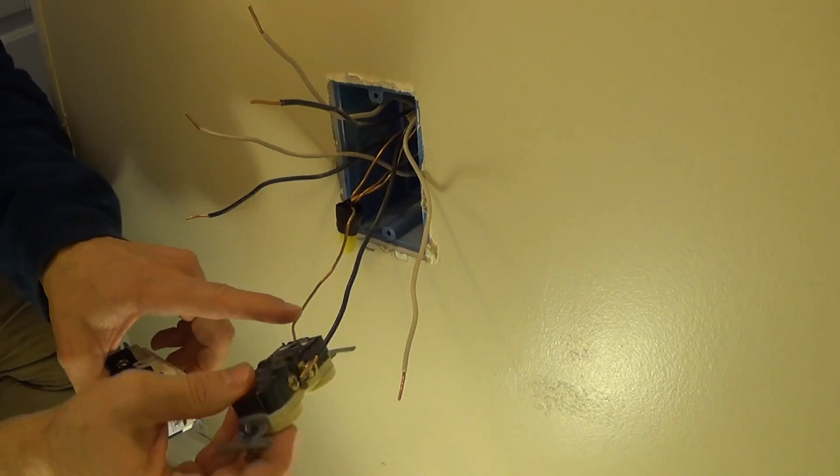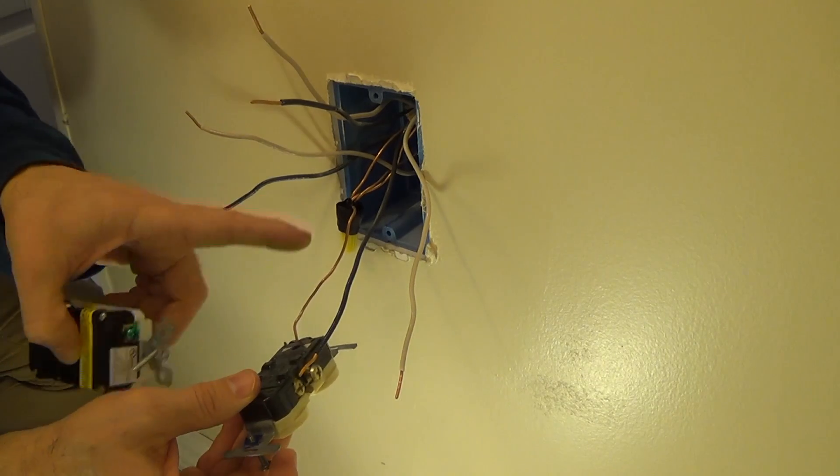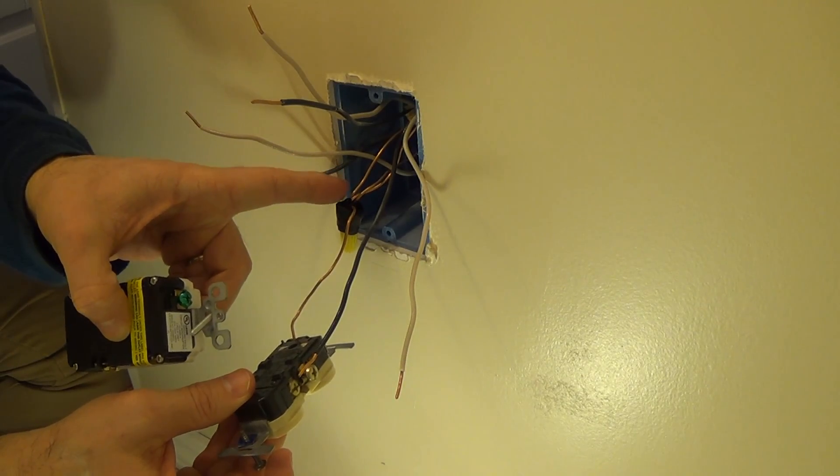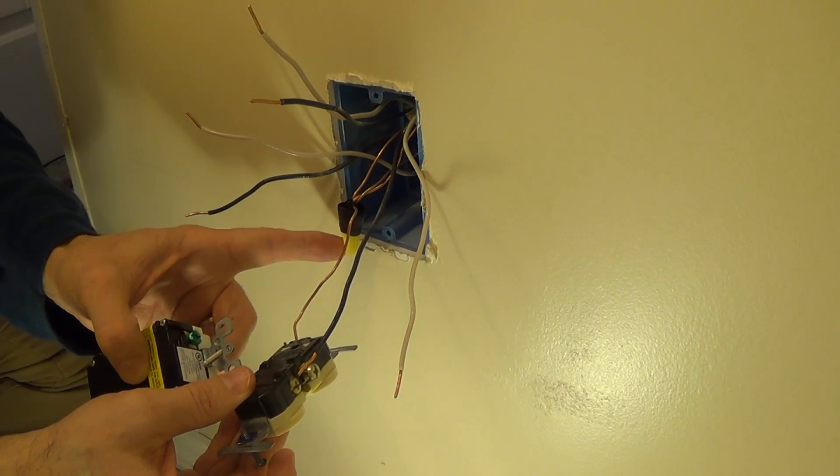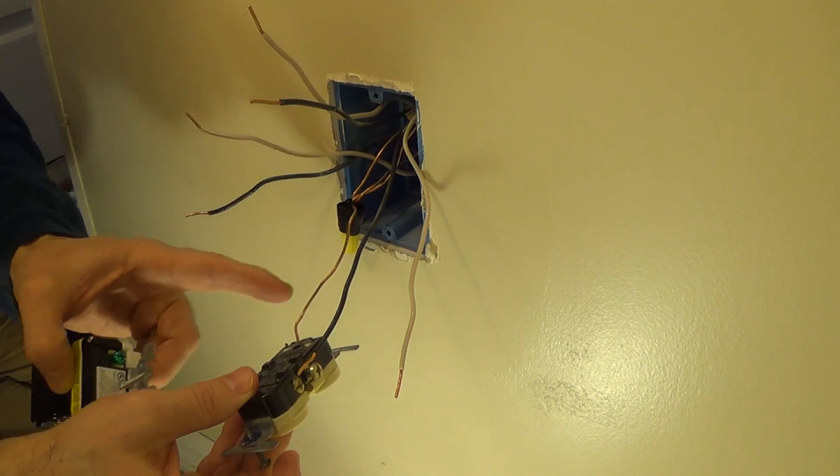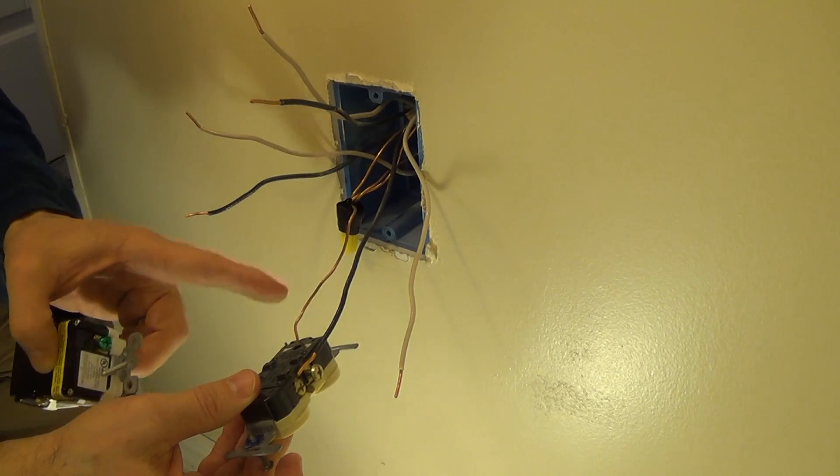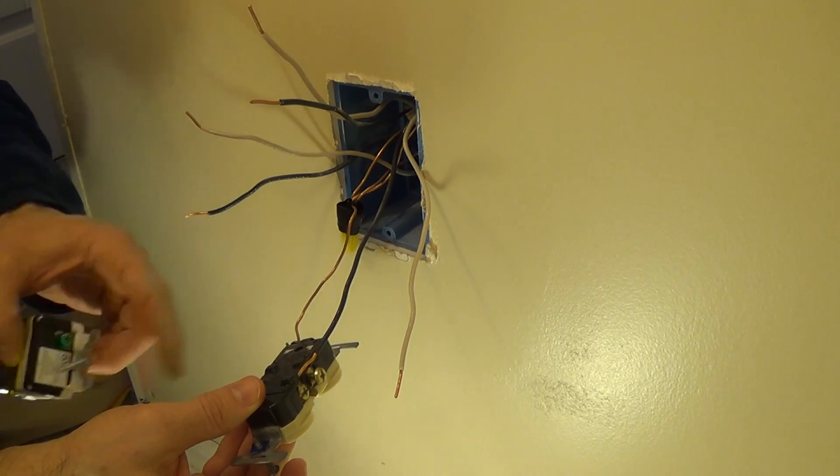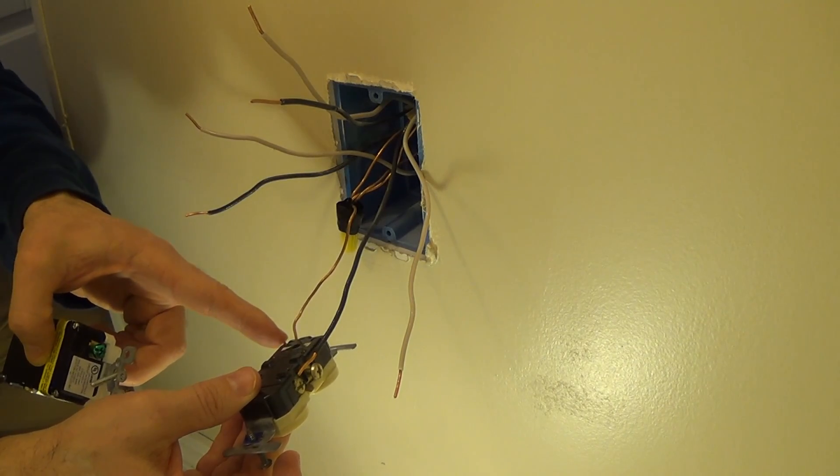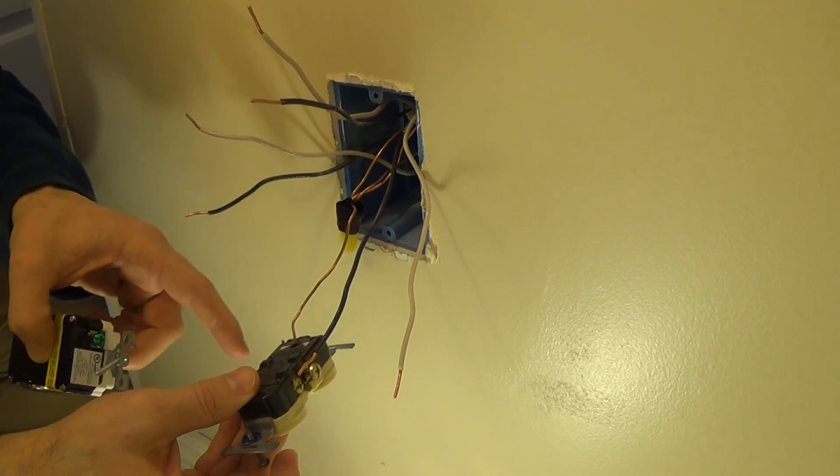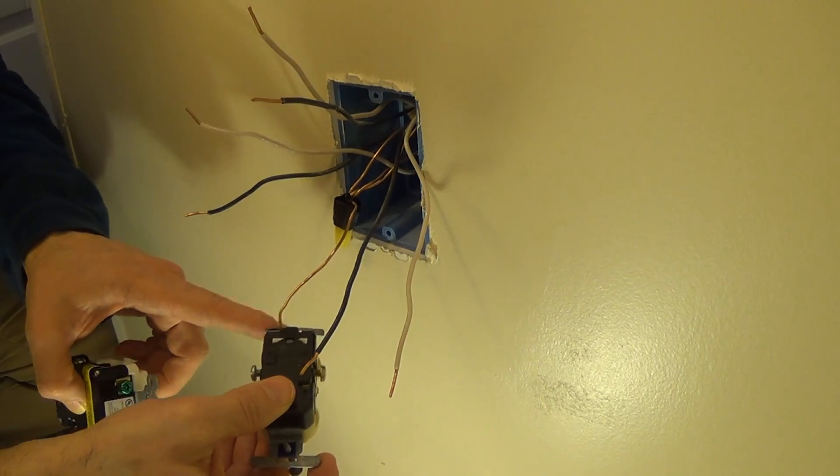This one that I took out, the standard receptacle, has what's called a pigtail for the grounds. You have three grounding wires here. It's connected with a little cap, a wire nut, and then you get a main wire coming in. This is generally per code and this is generally how you wire those things up. If you see a bunch of grounding wires in one terminal, that's wrong. You should really have a pigtail just like this.